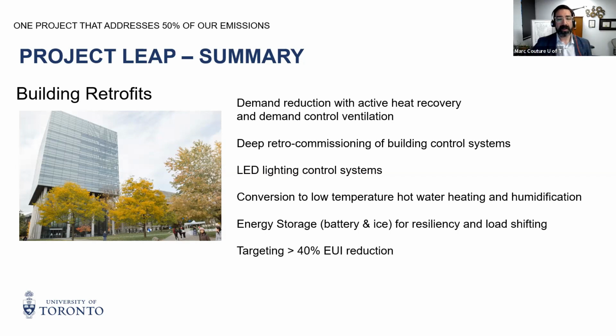In these lab buildings, with a lot of 100% fresh air systems that are very energy intensive, we're looking at strategies such as active heat recovery, using heat pumps to subcool the exhaust and use that exhaust stream as a heat source redirected toward heating these buildings and the rest of the campus. We're also looking at deep retro-commissioning of these buildings for optimization and control strategies to further reduce energy use intensity.